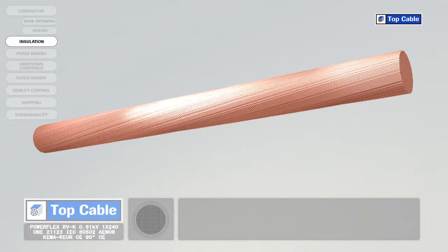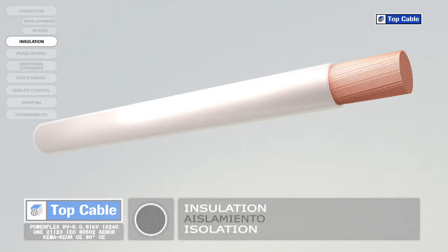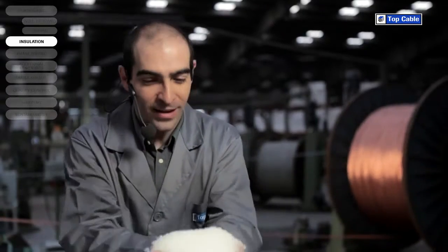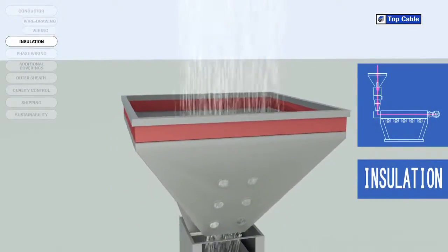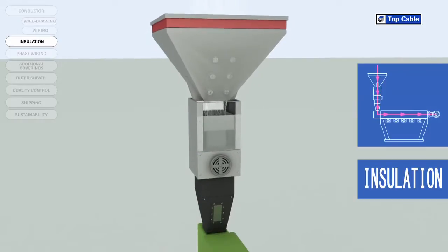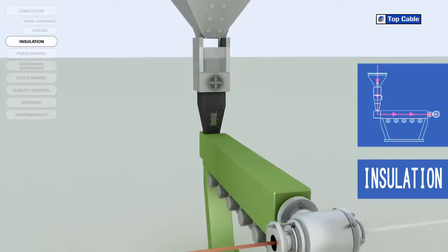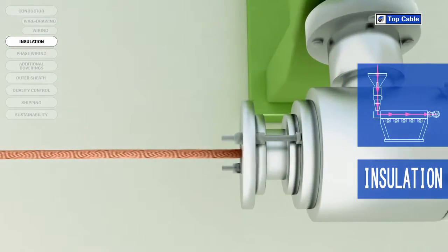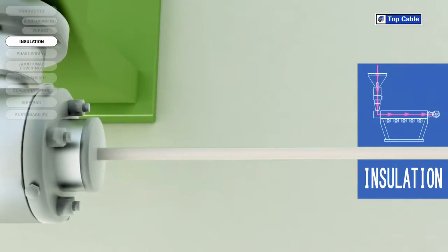The next process in the manufacture of electrical cables is the insulation. This is when we place an insulating cover over the conductor to prevent current leakages. In this process, the insulating material is added by a process of extrusion at high temperature. Several insulating materials may be used – PVC, EPR, XLPE, etc. Different insulation materials may be used depending on the characteristics of the cable required.